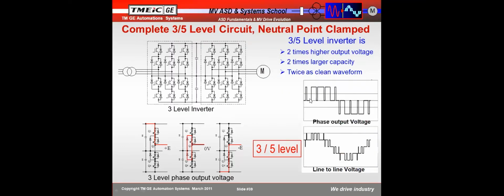Now I've got my 2-level drive up here, but now down here I'm showing you a 3-level drive. A 3-level drive takes more semiconductors, and therefore that's why we can't afford it in low voltage. So this is a 3-level drive that gives you 3 levels from 0 to peak and 5 levels from peak to peak. You'll notice there's our 0 voltage, and so that's 1st voltage, 2nd voltage, 3rd voltage. There's 3 levels, and that is a huge advance in technology, because now you're only turning on half of that voltage at a time. So the motor is only seeing half voltage at a time. It's much easier on motor insulation, which we really need in a medium voltage drive.